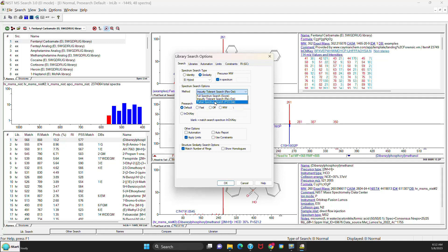The final is a new option. It's called the partial spectrum search. And it's somewhat the opposite of the impurity tolerant or reverse search in that if your unknown was absent some peaks when it does the library search, its match would not be penalized because those peaks were absent. This is probably less useful in EI, though you might find some options that would be good for doing an EI search. But it's very useful for doing MS-MS in which the library spectra are not quite as reproducible because they're based on energy and they might be missing some peaks. So you might find that useful for doing that type search.